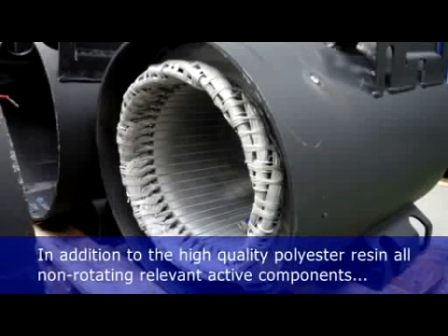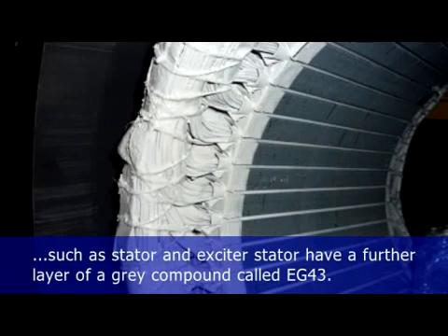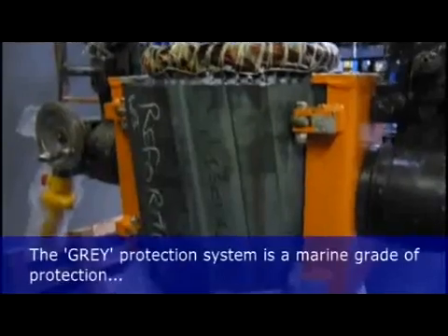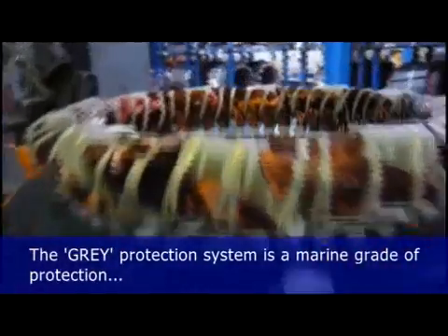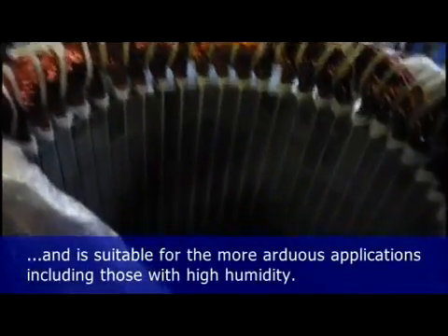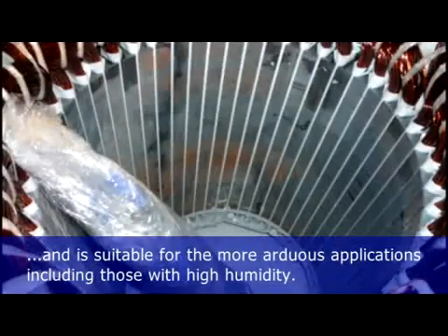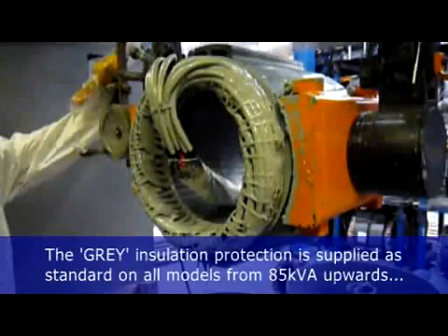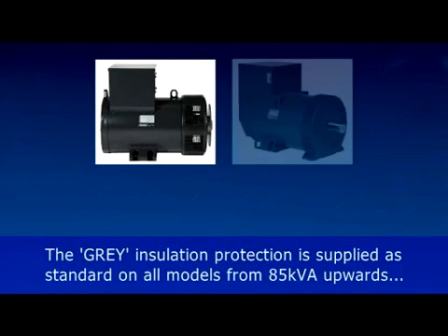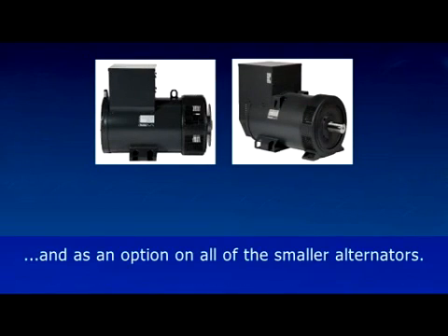In addition to the high-quality polyester resin, all non-rotating relevant active components, such as stator and exciter stator, have a further layer of a grey compound called EG43. The grey protection system is a marine grade of protection and is suitable for the more arduous applications, including those with high humidity. The grey insulation protection is supplied as standard on all models from 85 kVA upwards, and as an option on all of the smaller machines.